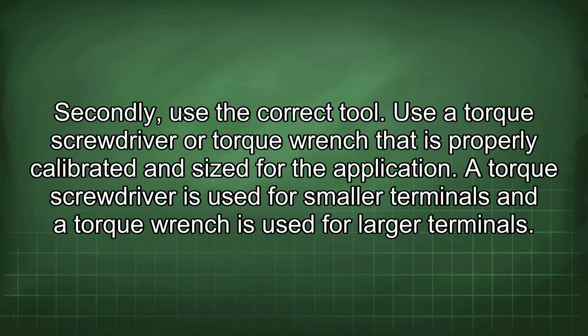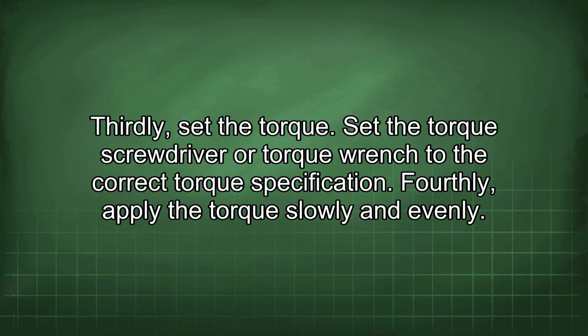Secondly, use the correct tool. Use a torque screwdriver or torque wrench that is properly calibrated and sized for the application. A torque screwdriver is used for smaller terminals and a torque wrench is used for larger terminals. Thirdly, set the torque. Set the torque screwdriver or torque wrench to the correct torque specification.